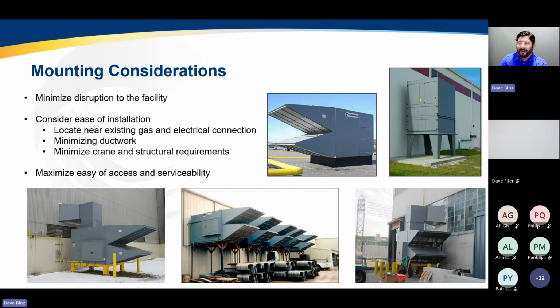And so I always used to say, use what the building gives us. And so if we've got space outdoors, let's put the unit on pads and duct in. We're not really putting any load on the structure. A simple pad or stand outside can do minimal building modification changes. Maybe I need to install some units in the roof because I don't want to have large, extensive use of ductwork. We've got a variety of ways to apply those equipment, vertical, horizontal, rooftop, pad mounts, indoors or outdoors. Maybe some locations they want to put the unit indoors and just provide my hood outdoors. But you've got a lot of options, and every building and every end user may actually have different requirements that you need to work with.